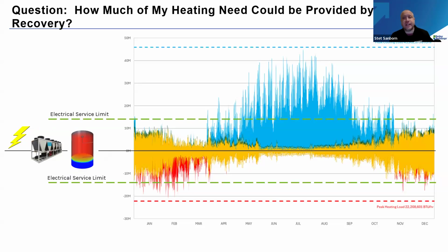Next. So this is an example of if you are running into an electrical service limit on your project, which typically occurs on the heating side. This particular project doesn't really have one on the cooling side because that chiller was already in place. But if on the heating side, we're running into that limit, you can see that those red lines get past that electrical limit only for a few hours. That's a beautiful place for storage to be paired with your heat pump, because all those hours that you're not crossing that green line, your heat pump is charging that tank. And then for the few hours that you go past it, the heat pump plus the tank can operate in parallel and provide that peak load. So it's a really great solution. Next slide.